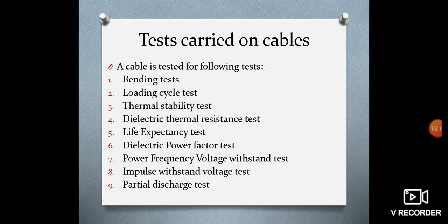Then we have the cable's impulse withstand voltage test. Cables are tested for power frequency AC and DC voltages. During manufacture, the entire cable is passed through a higher voltage test than the rated voltage to check the continuity of the cable. As a routine, the cable is subjected to a voltage 2.5 times the working voltage for 10 minutes without damaging the insulation of the cable.